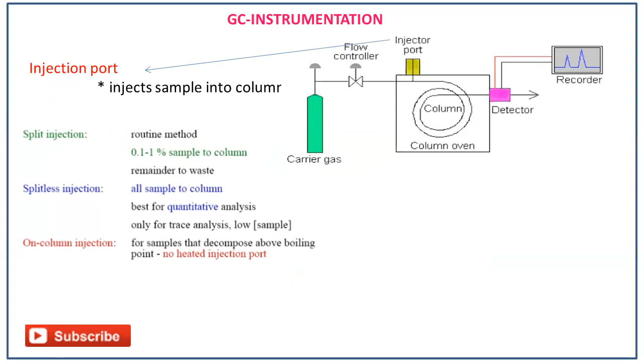So what is this split injection? The picture that we can see here is about the split mode. Before explaining the split mode, I'm just explaining the construction of this split injection. This is the way that we send the carrier gas, and this is the injection port, which is connected to the column, and here there is a split valve. If you are sending excess sample through this, then the excess sample gets separated and goes out through this valve. That's why the split valve is open here.